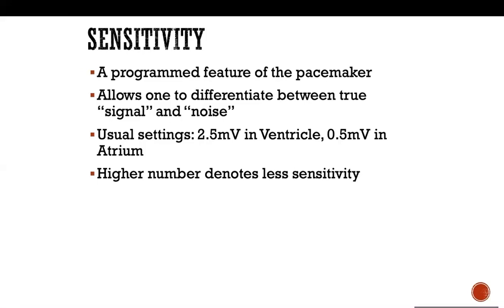So the sensitivity is that anything above this number, the device is going to see. So we measure the amplitude of the R wave on the ECG. It's not the ECG, but it's a similar concept of measuring the R wave on an ECG. You measure the R wave from the lead itself, and it's going to give you a reading. For example, if you measured the voltage of a QRS on an ECG, we would say this is maybe high voltage because maybe it's more than 10.